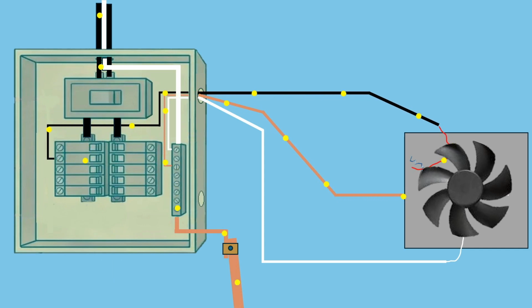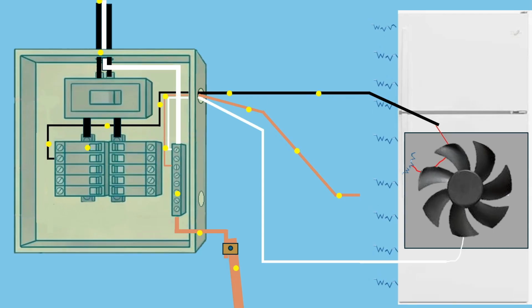So even though the ground rod is connected to the electrical system, it cannot carry enough current to clear a fault. That means if the ground rod were the only return path for fault current, the breaker would never trip. The metal frame of the appliance could remain energized indefinitely, creating a serious shock hazard. This is why grounding, or earthing, cannot clear electrical faults. The earth is simply not a low-resistance path.